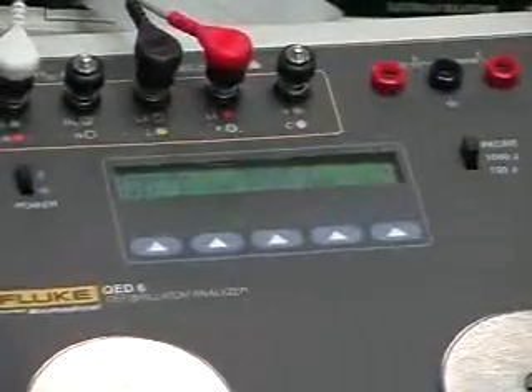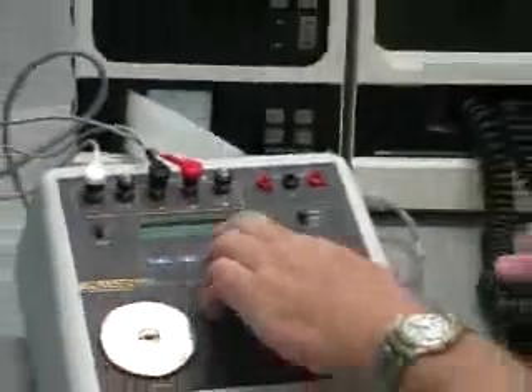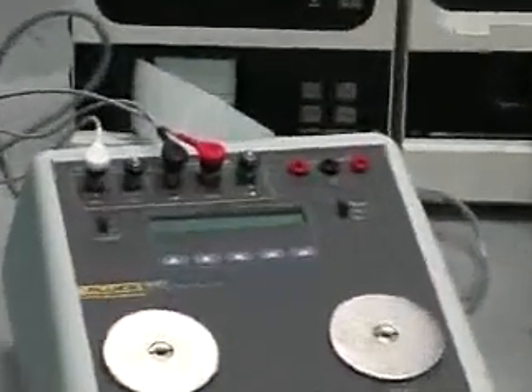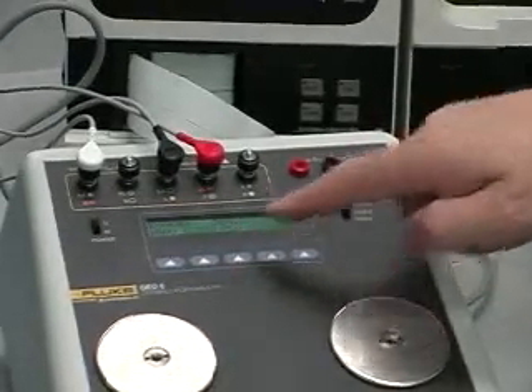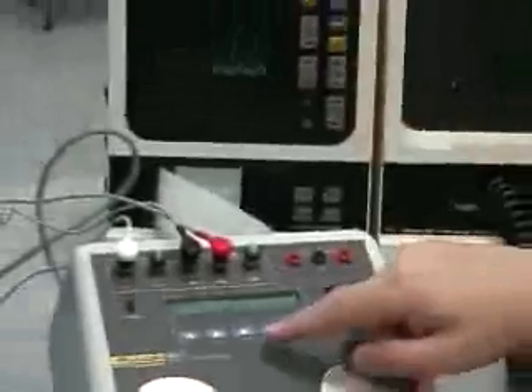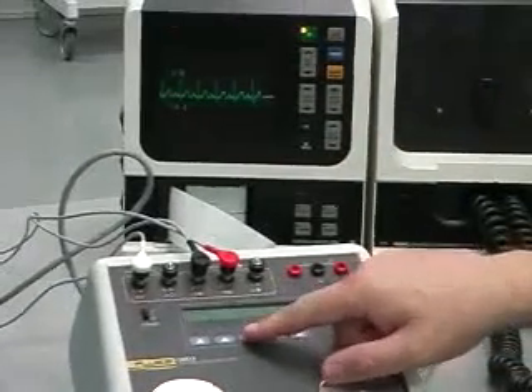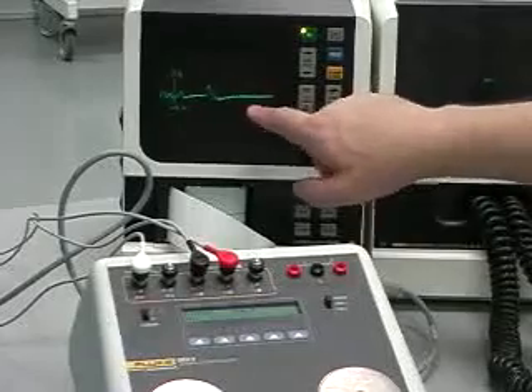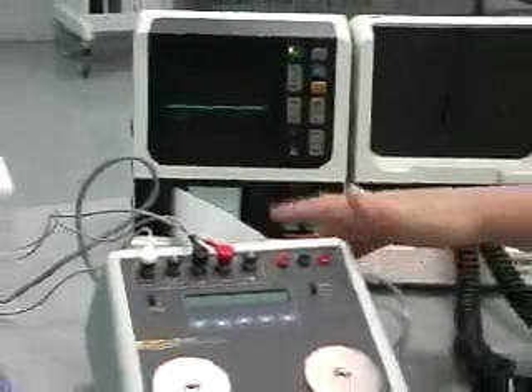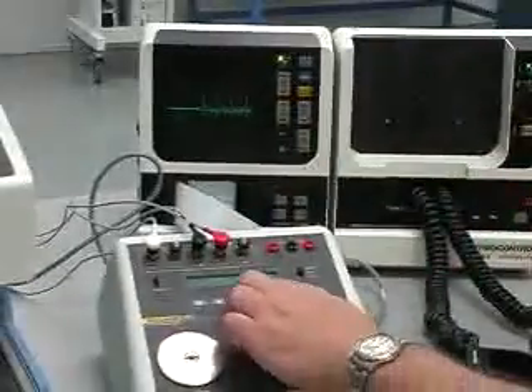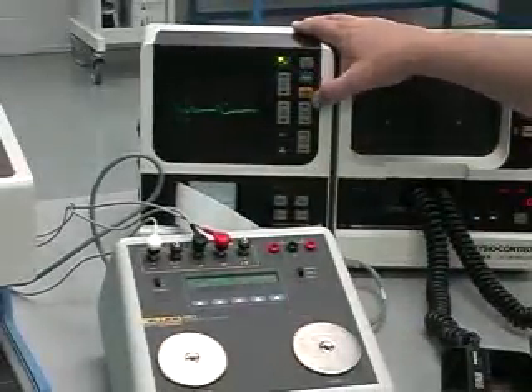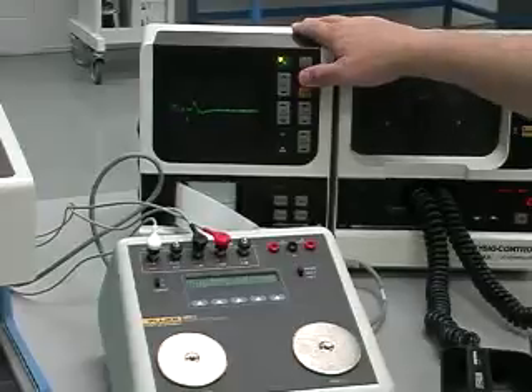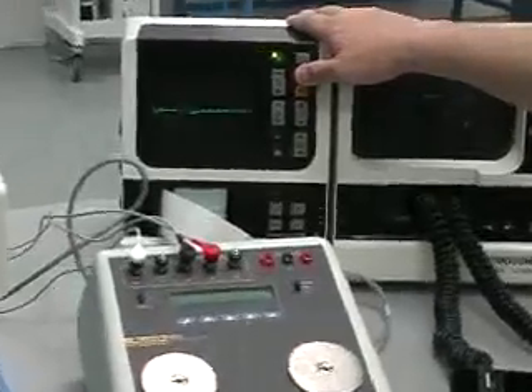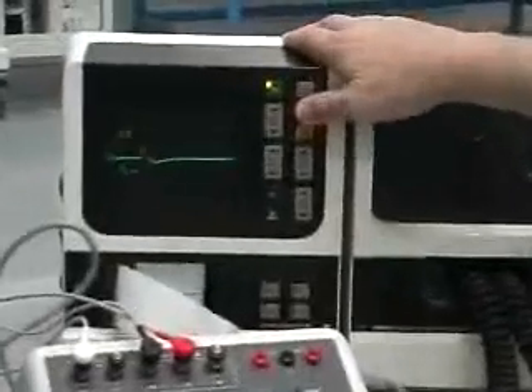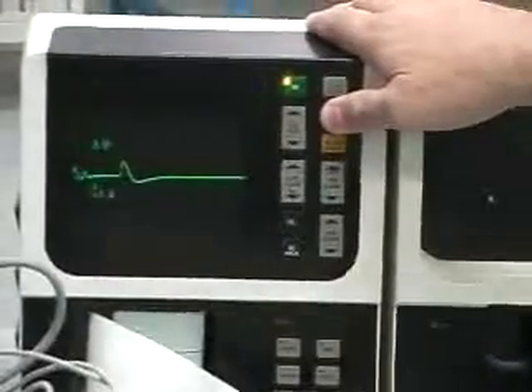Okay, 364.9, again in good shape. And you can then push the play button, and that will then discharge or replay the waveform that you have stored in the analyzer. And that is the waveform for the monophasic discharge defib.